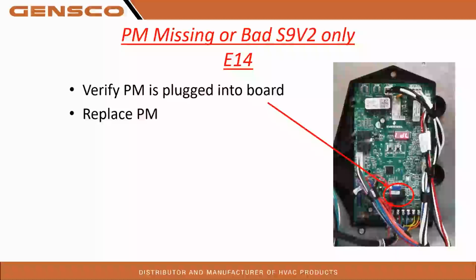All right, almost done here, guys. So PM missing or bad, S9V2, that's an E14. So the personality module is not on the board. Honestly, we get this call very rarely. When we do, it's typically, well, I just replaced the control board and now I'm getting an E14 error. Okay, what did you do with the old control board? Well, it's still in my van. Okay, we'll go get the personality module off of it and put it on the new board.